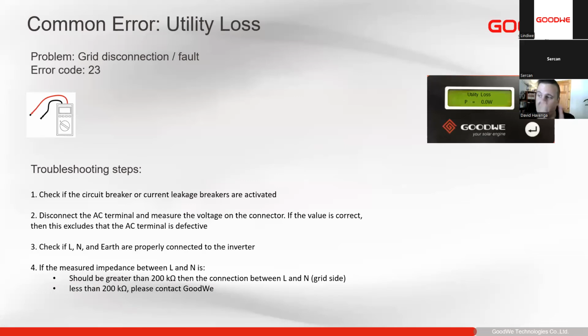And lastly, if we can confirm that the inverter is receiving the grid voltage, but it's still saying utility loss, then we can measure the impedance of the grid port on the inverter, and it should be greater than 200 kilo ohms between live and neutral. If it's not, please contact us for support.